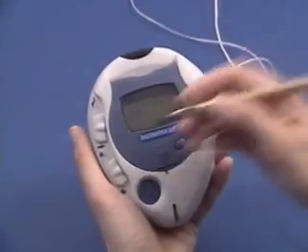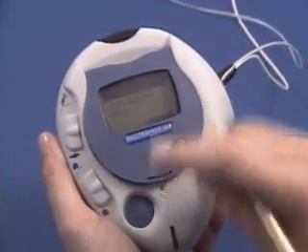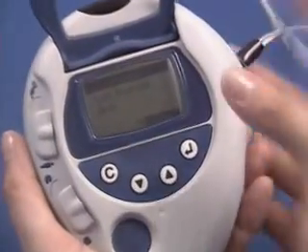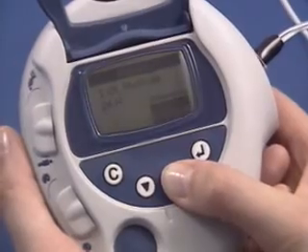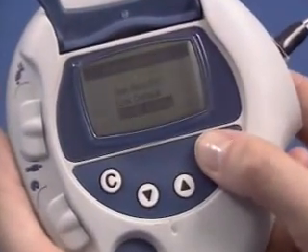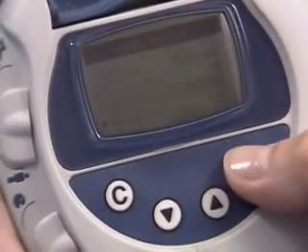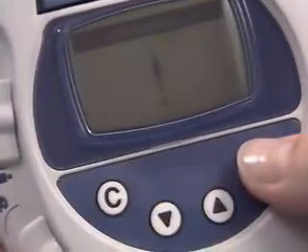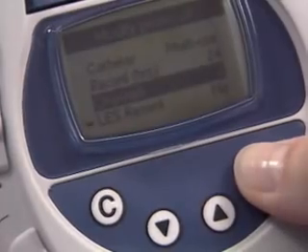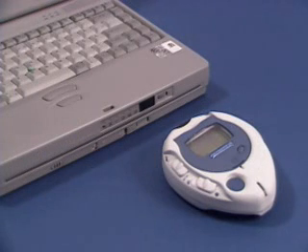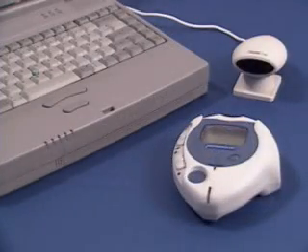The operator control keys are used to control the unit's menu system. They are concealed to prohibit patient access. You will only need to use these keys occasionally. For more details, consult your daily use manual. Displayed on the screen are various operator and patient instructions dependent on operation mode. The study data is transferred to the computer via infrared communication, either through a built-in port or using a dongle attachment to the computer's serial port.